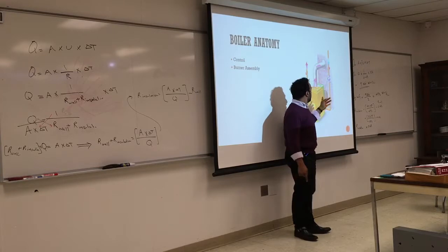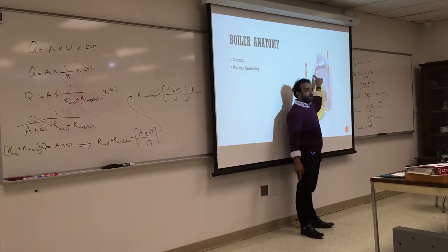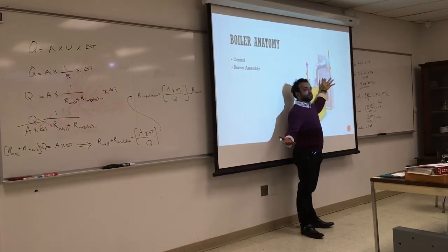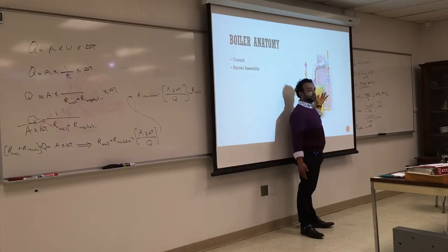Efficiency goes down, and if you stick your thermometer here, it will show you 600 degrees. What is the burning temperature of oil? 600 degrees. What is the exhaust? 600 degrees, which means what? You didn't lose anything. You didn't absorb anything.